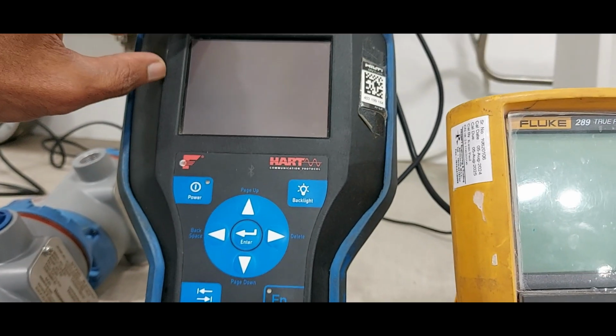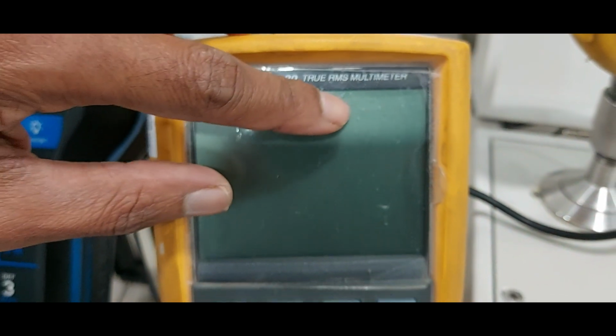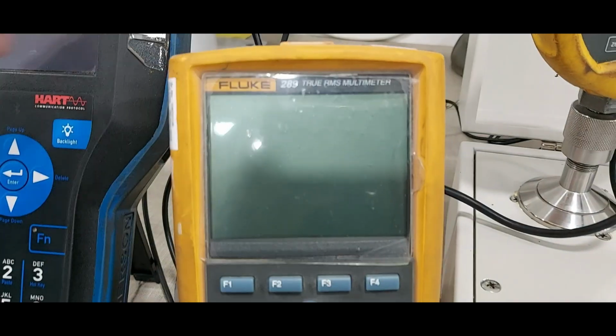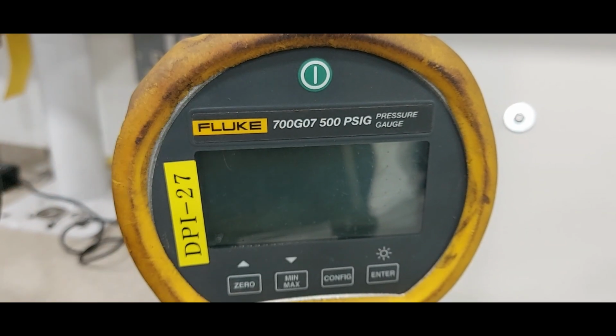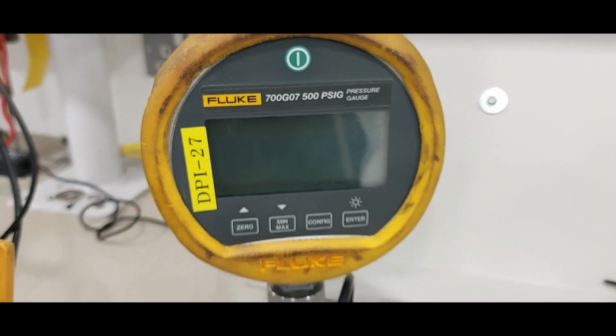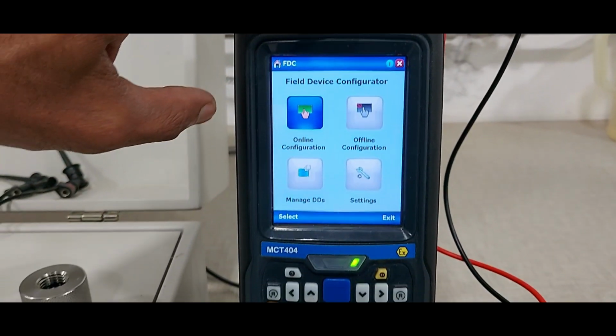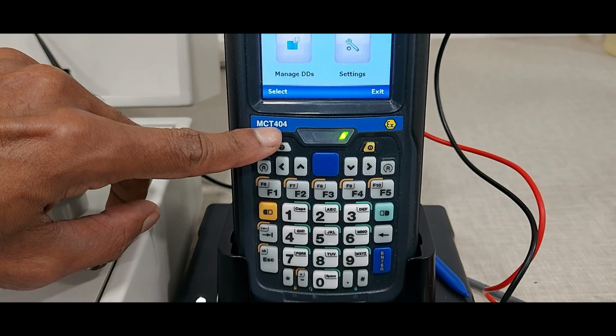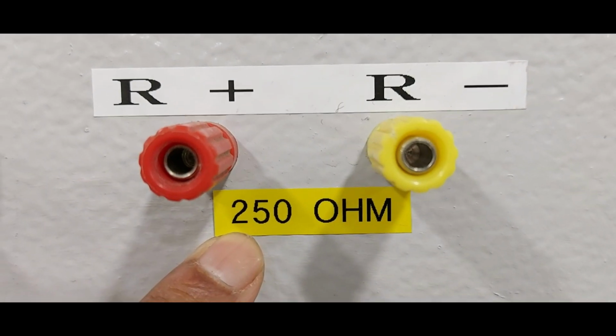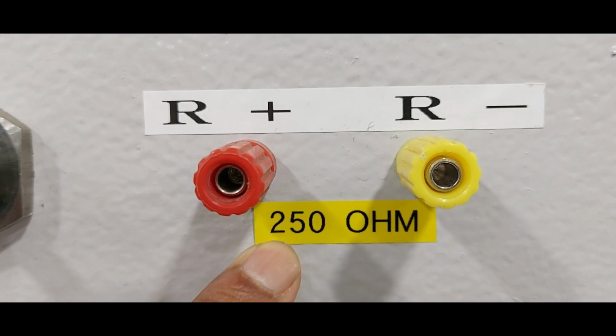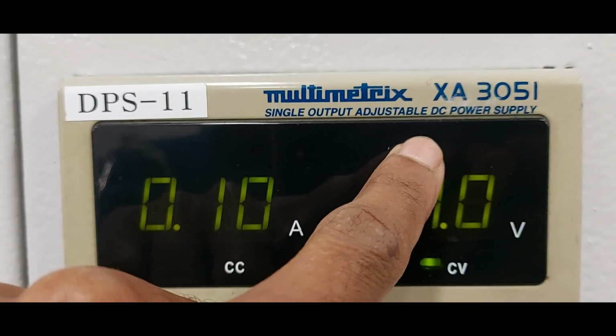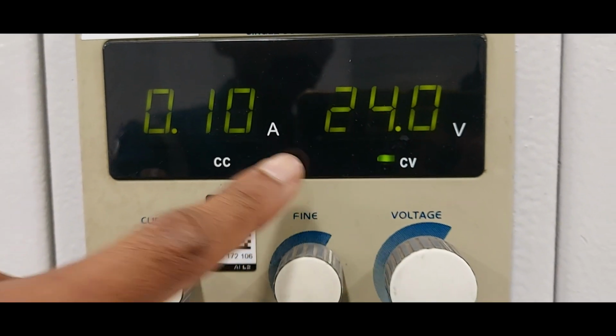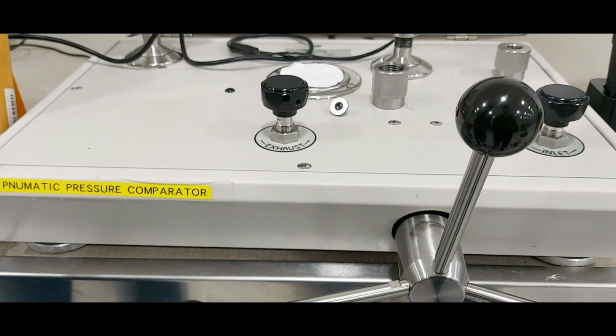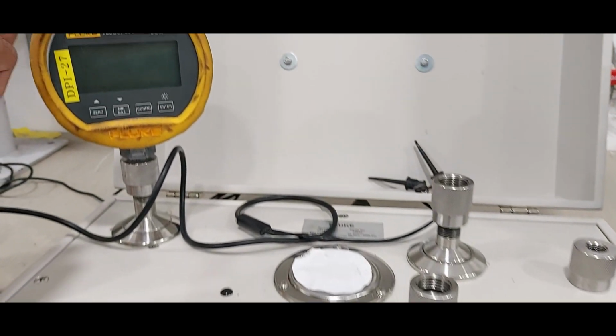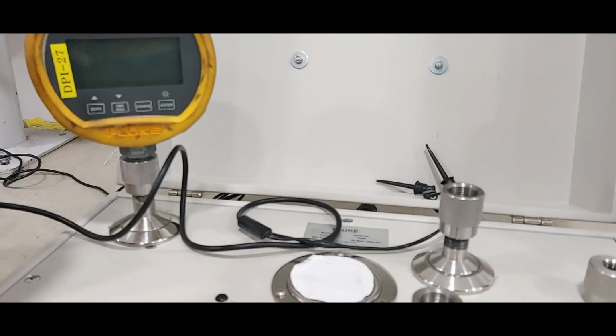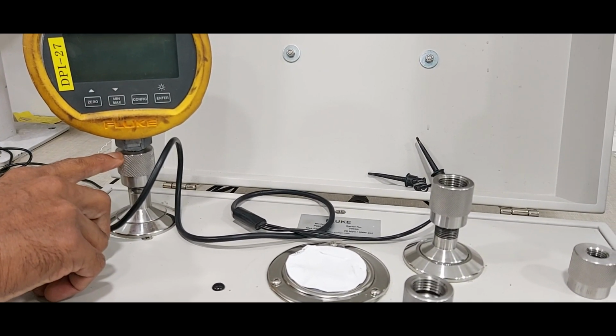Minimum required: one field communicator, RMS multimeter, gauge, reference gauge. Configuration purpose: Honeywell MCT404 communicator, 250 ohms resistance, adjustable DC power supply 24 volt, pneumatic comparator, reference gauge connected to output line.